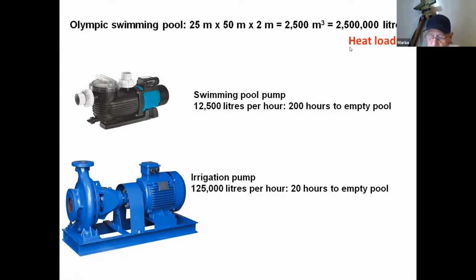This is analogous to the cold room situation, where the water in the pool represents the heat load. A cooling system is nothing other than a heat pump. It's pumping heat from the warm fruit to the cold air circulating around the fruit. That cold air transfers the heat it's taken from the fruit to the refrigerant, and the refrigerant transfers it in the condenser outside the system to the air outside the facility. So you're basically pumping heat from the fruit to the outside environment.